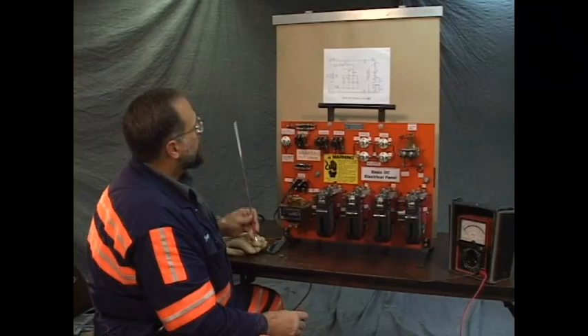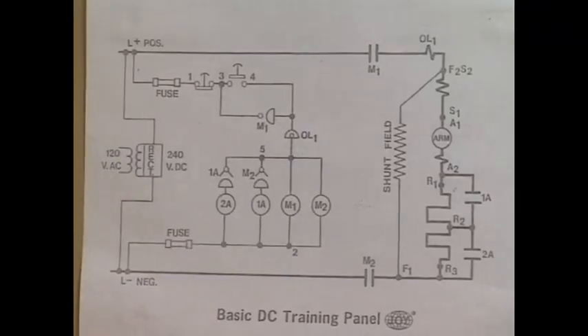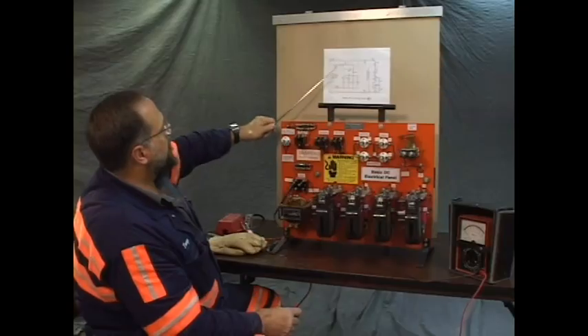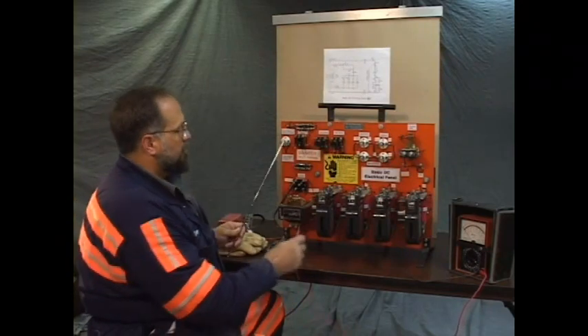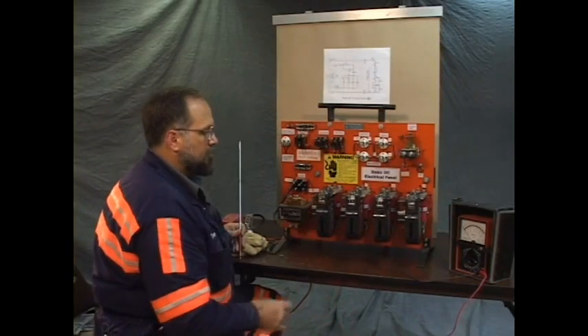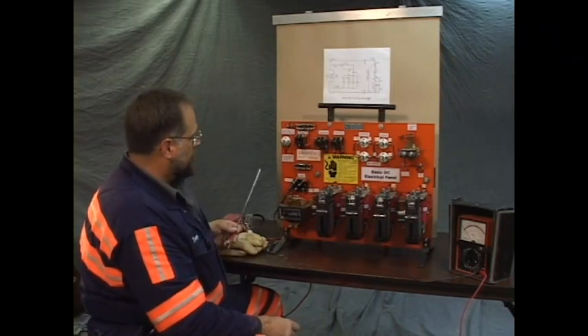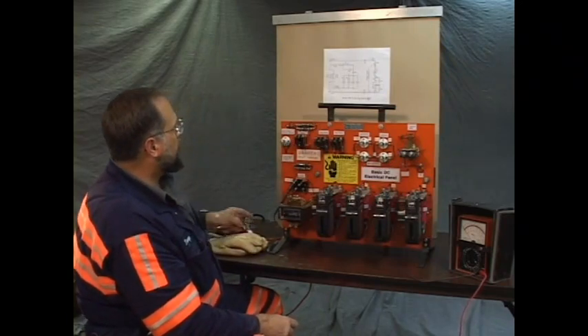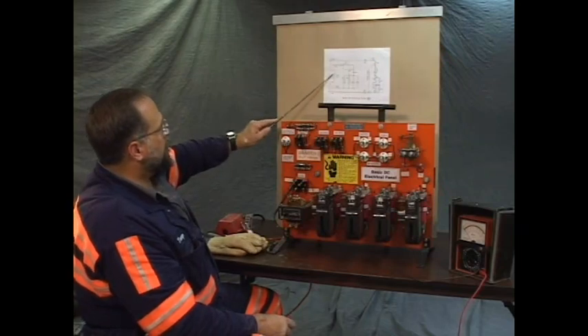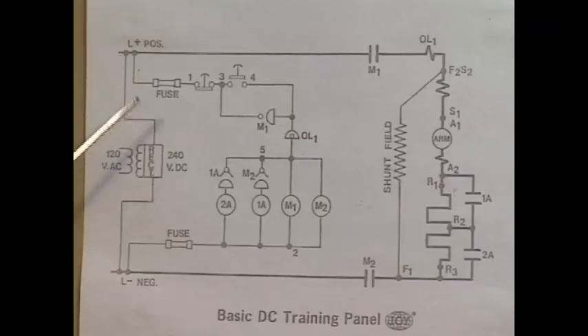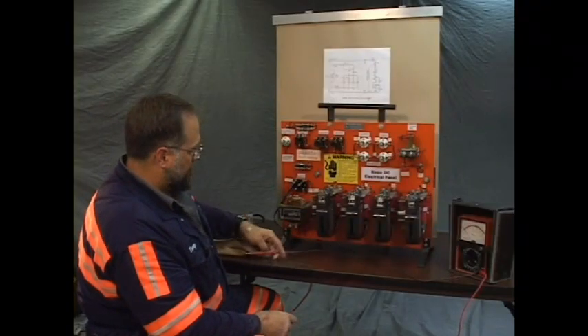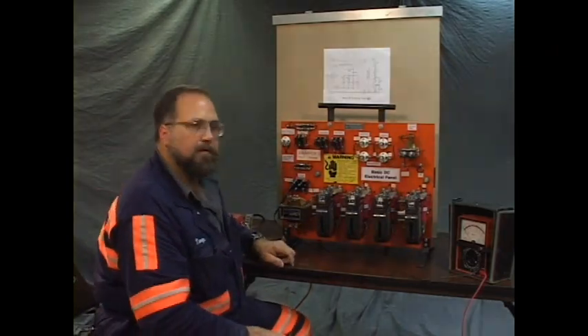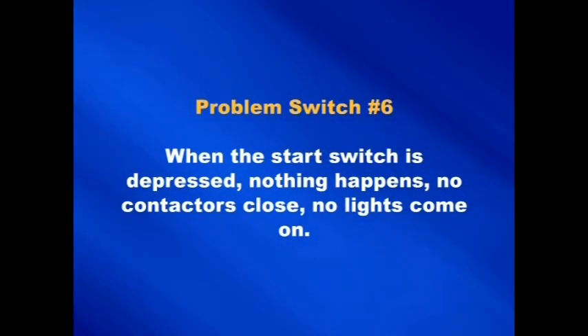Now, our meter's functioning, but the first point that we go to from the rectifier to the top front of M1 starter, there's no circuit. And that's our problem. We have an open wire from the positive terminal of the rectifier to the top front of M1. That's that. Should the apprentice electrician draw problem card number 6 at the testing center, this is what he'd have.